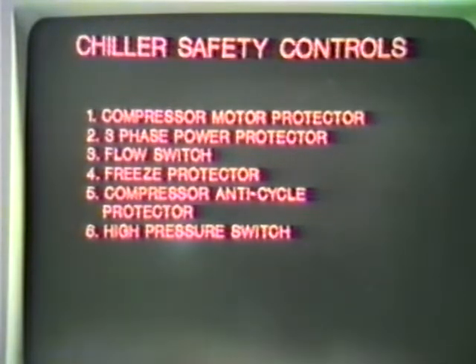There are numerous operational safety controls to be aware of. These are outlined and discussed thoroughly in the operating and maintenance manual on pages 22 through 29. These are safeties such as the compressor motor protectors and the three-phase power line monitor. This is a device that protects the compressor from single phasing, in case one leg falls out. Also a chilled water flow switch, an evaporator freeze protection switch, a compressor anti-recycle protector, and high pressure switches. These are all very important items in the routine operation of the chillers.